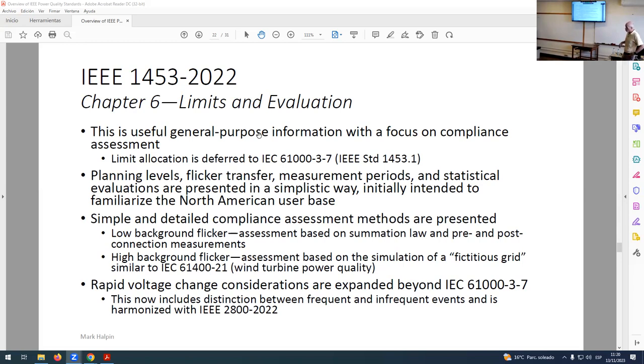Well, what's in 1453, and this is a case where I don't personally agree with it, but what's in the document is, if background flicker levels are high, then assess an individual customer's contribution based on simulating the so-called fictitious grid. Now, if you're familiar with the IEC 61400 Part 21 document, the power quality for wind turbines, that's where that comes from. That's the IEC recommendation for assessing not just flicker, but power quality effects in general for wind turbines. And that is a very tricky thing to do.